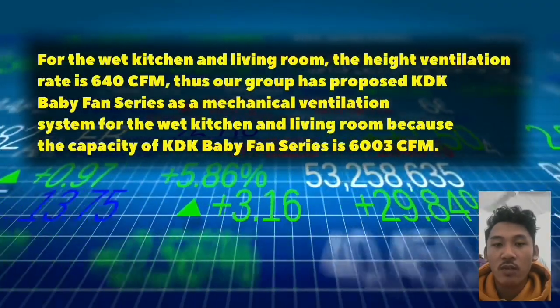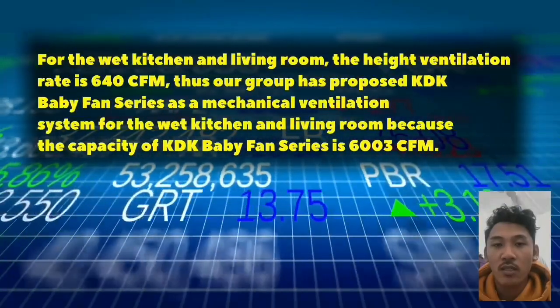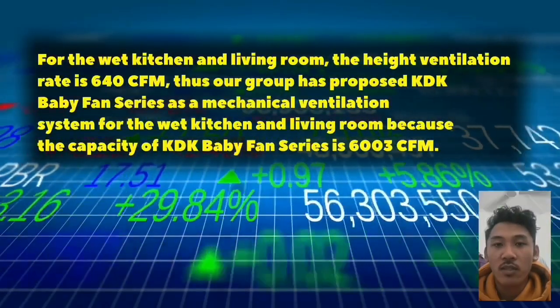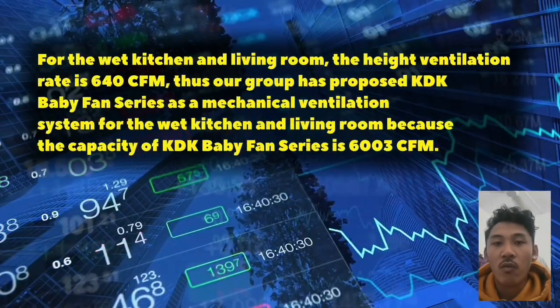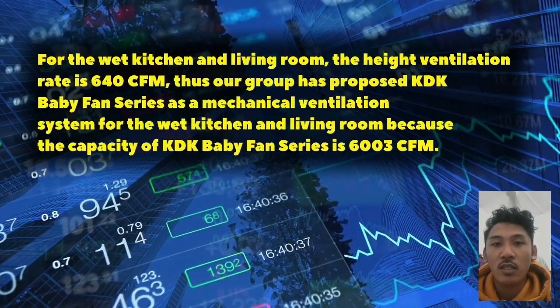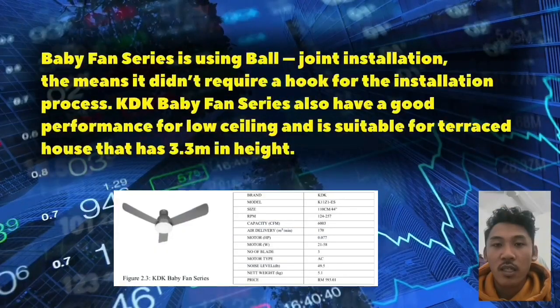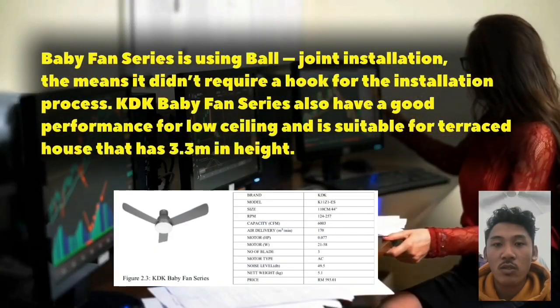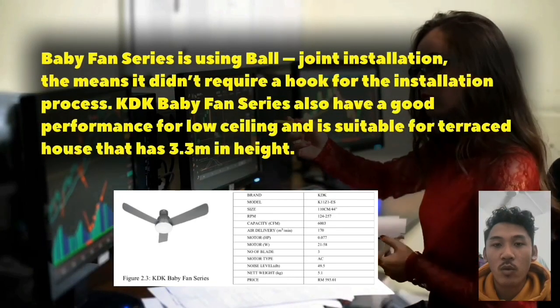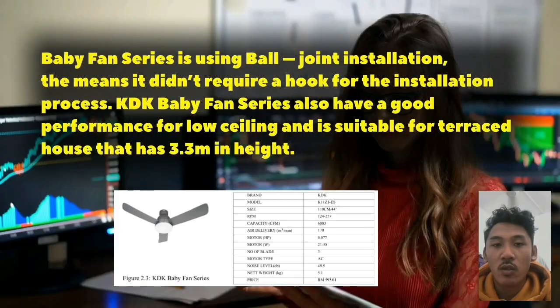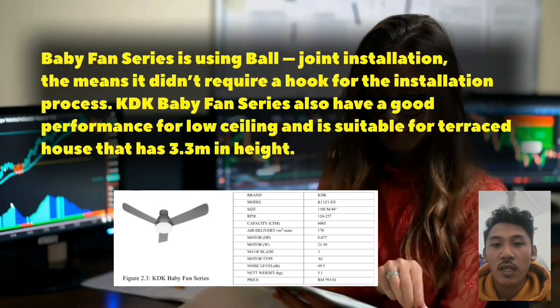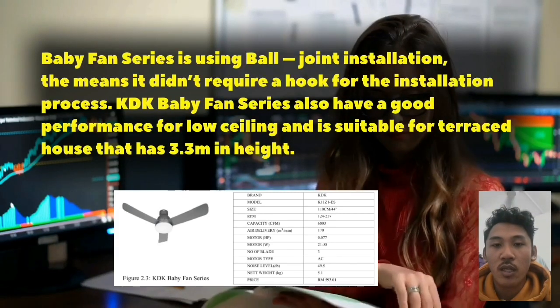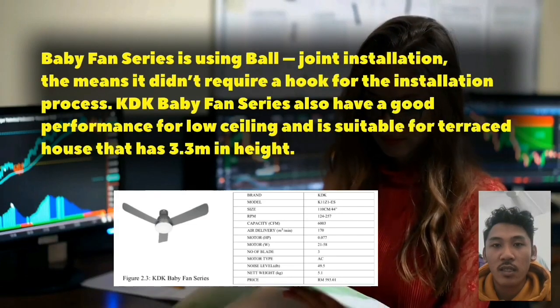For the wet kitchen and living room, the highest ventilation rate is 640 CFM. Thus, our group proposes the KDK Baby Fan Series as the mechanical ventilation system for the wet kitchen and living room because its capacity is 6003 CFM. The KDK Baby Fan Series uses ball joint installation, which means it doesn't require a hook for installation. It also has good performance for low ceiling and is suitable for a terrace house that is 3.3 meters in height. That's all from me. Thank you.